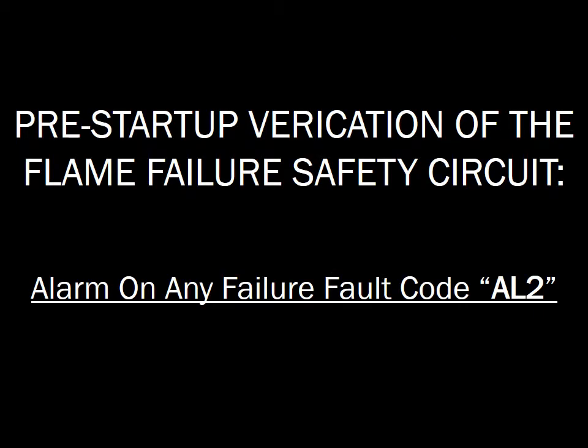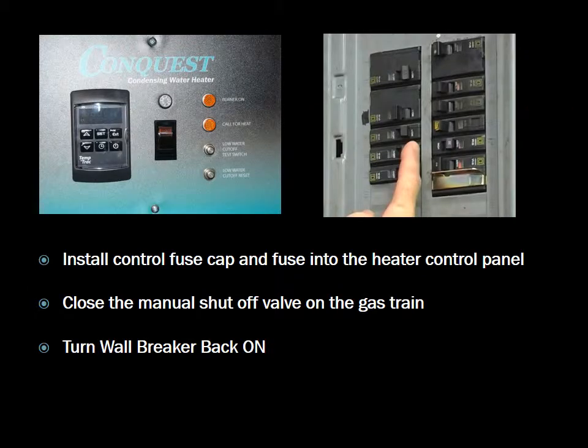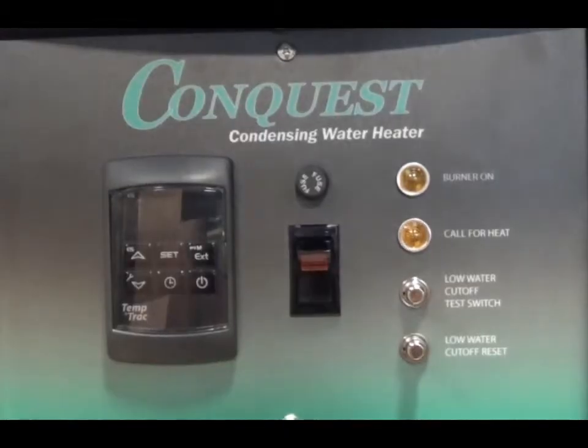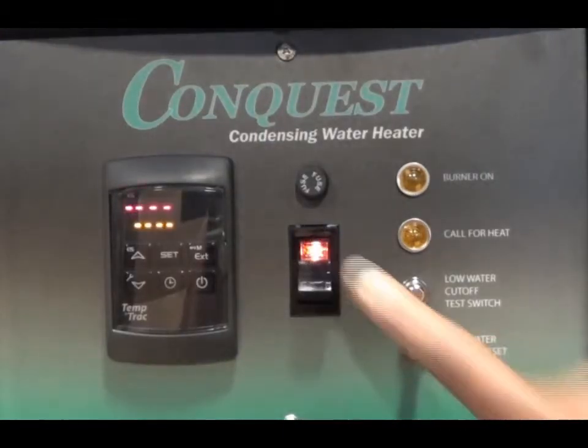Before attempting to start the water heater, the alarm on any failure feature in the flame safeguard safety circuit must be verified. First locate the control fuse cap and fuse and install it into the water heater control panel. Now close the manual shutoff valve on the gas train. Power the unit by switching the wall breaker on. Energize the Temptrac control by turning the unit's power switch to the on position.